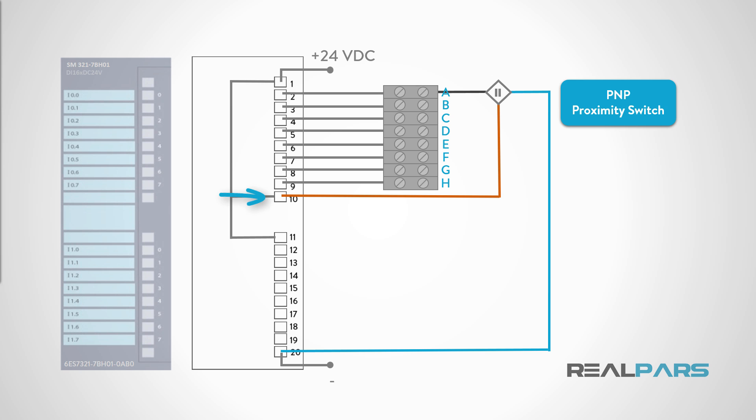24 volts DC will be obtained from terminal 1. Terminal 20 is connected to the power supply DC common. For a PNP device, care must be taken to connect the brown wire to the 24-volt DC terminal, and the black wire to the PLC input channel terminal. If we connect the proximity switch to PLC input channel 3, then the black wire will land on terminal D. Finally, the blue wire will be connected to the power supply DC common, terminal 20. When the proximity switch senses an object nearby, the state of the switch will change, and the input channel to which the proximity switch is wired will indicate an ON state. Both the electronics in the switch and the PLC card are powered by the same 24-volt DC power supply.